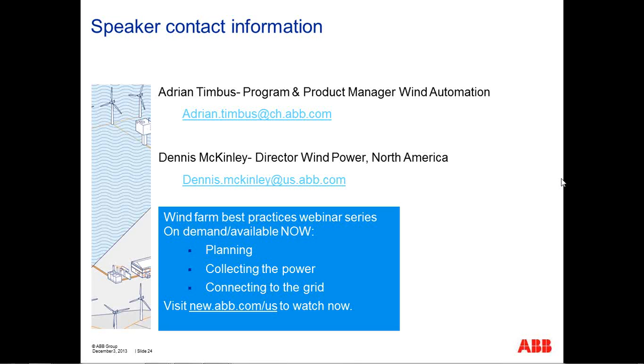Okay, very good. What is the more common operating mode: voltage control or power factor control? Well, that really depends on the area where the plant operates. What we see in Europe is that power factor control is requested to be primarily the control mode for reactive power, meaning that every time the active power changes, the reactive power will change as well.